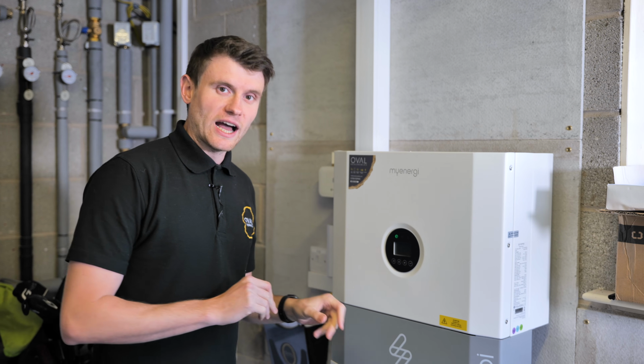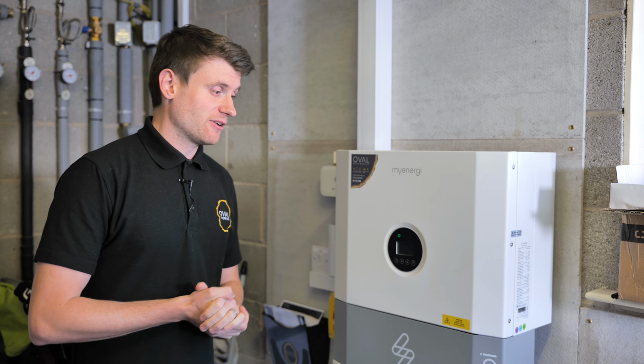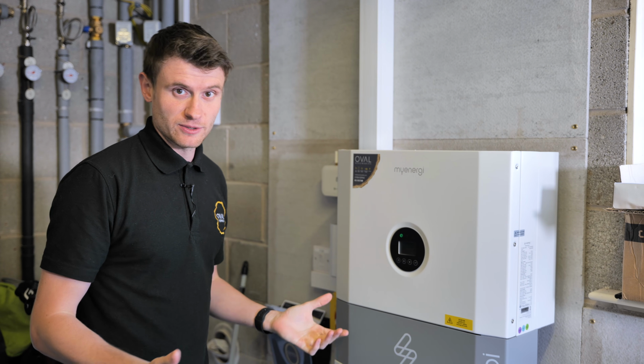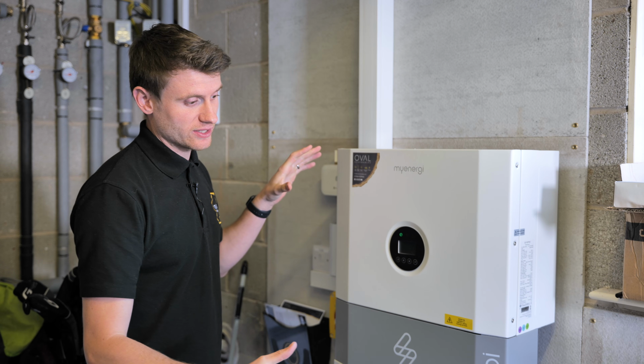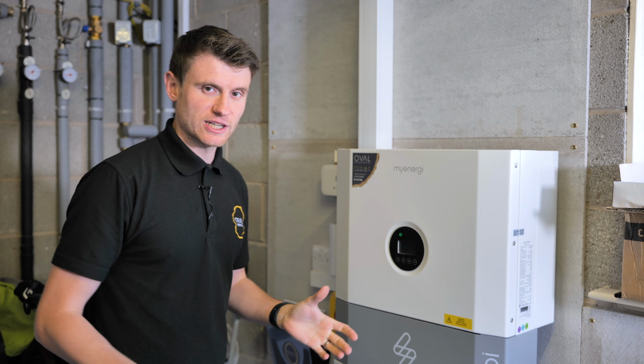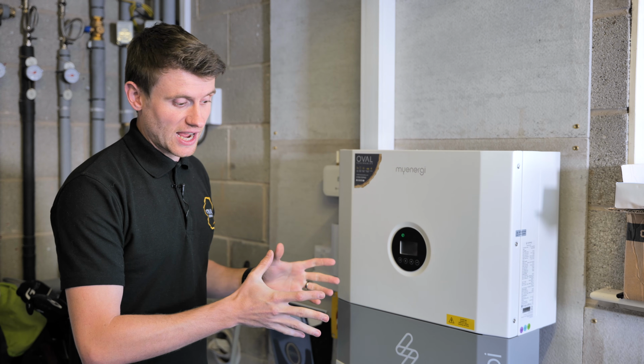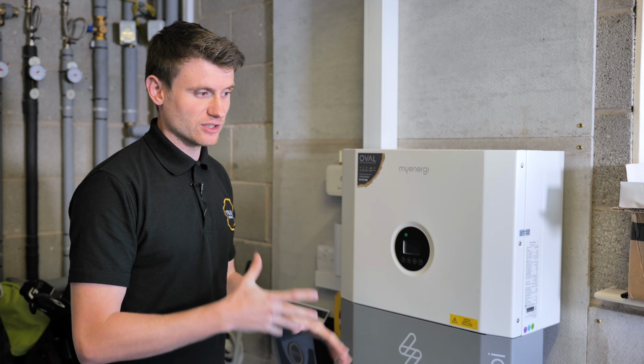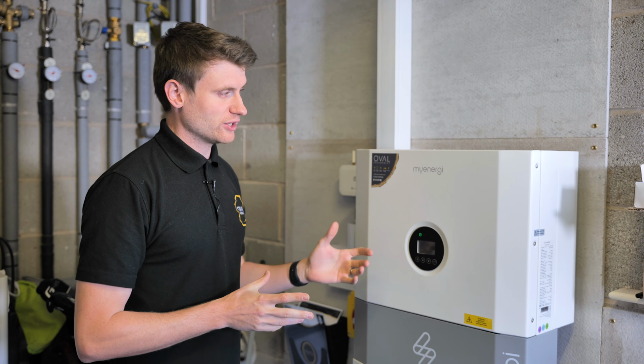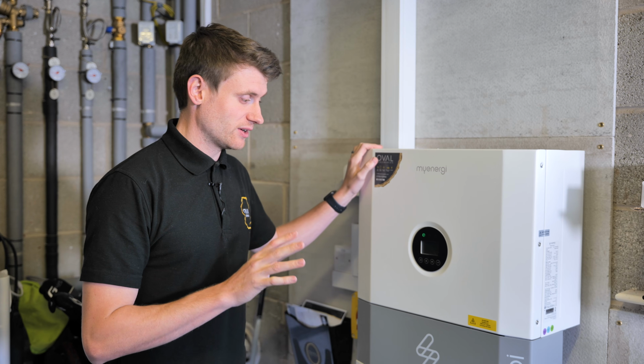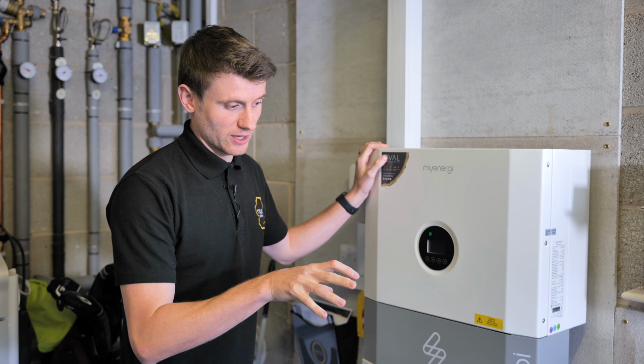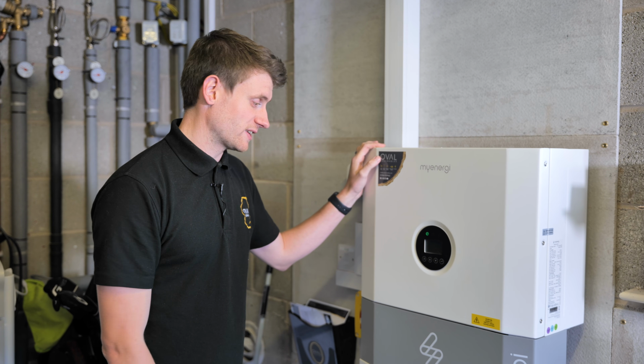I've just had a little look, and it is an IP65 battery module or battery system, so this could be installed outside in most cases. It's always up to the electrical designer to decide whether or not this can be installed outside and the location it goes, but it's got a really good ingress protection level of IP65. So for most scenarios it's fantastic.